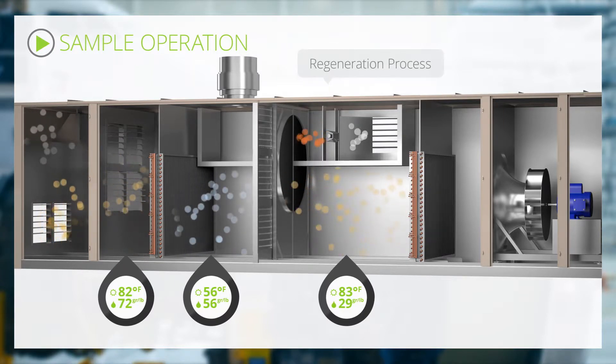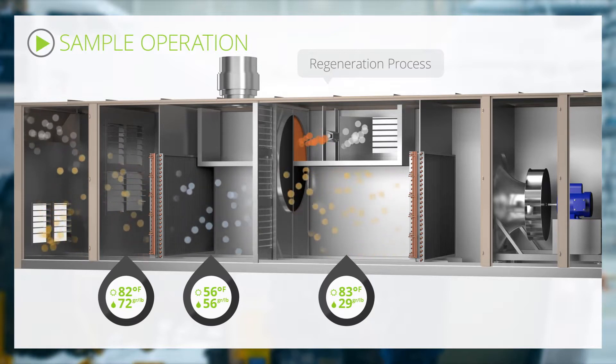Simultaneously, regenerative air is drawn through the natural gas-fired burner, heated and used to dry the absorbed moisture in the wheel before being exhausted out of the unit.